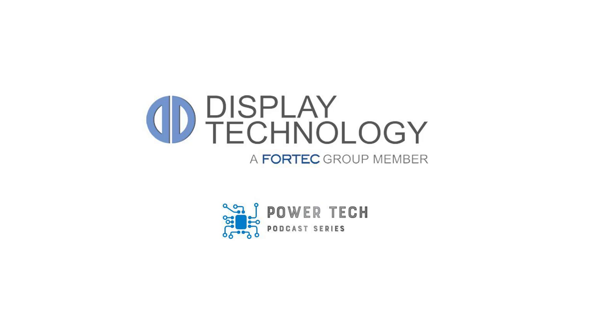Lastly, the fourth type of power converter is the AC to AC converter. It's also known as a cycloconverter. This converter converts an AC voltage from one frequency to another. These converters are often found in industrial and transportation applications where the frequency needs to be changed. It's often used in conjunction with an induction motor. It's because induction motors are controlled by frequency control.